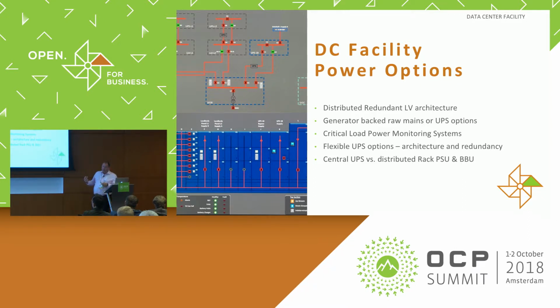What we tried to do is build in as much flexibility in our facility as possible. Because we're hitting a speculative market, we've gone for a centralized UPS within each data hall as the basis of design. We can flex that so we can just provide a raw mains and generator back-up supply to each hall, or we can do individual UPSs within the space, or even support the OCP rack with battery backup units. It really depends on who's going to go in there. So we'll talk to customers when they're coming in, especially if they're fitting out a new hall from a raw condition. But if necessary, we can switch out the UPS and redeploy into another suite if we need to.